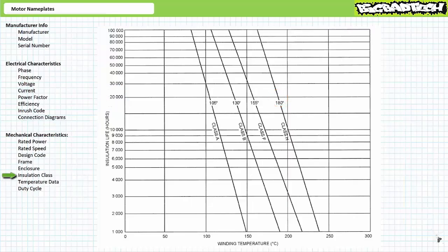One can estimate insulation lifespan at other than the standard temperatures using a chart like this. Let's say you've got a motor with Class B insulation, and you're operating it not at the standard 130 degrees Celsius, but rather an increased 150 degrees Celsius. If we find the intersection of the sloped B curve with the 150 degree Celsius vertical line and follow it horizontally to the left, we find this motor insulation will last only 9,000 hours. As one might expect, higher operating temperatures shorten the lifespan of a motor's winding insulation.